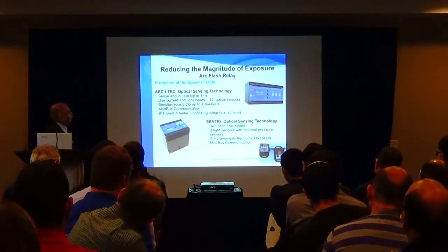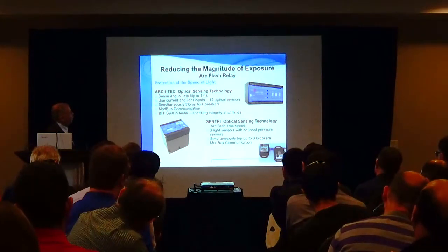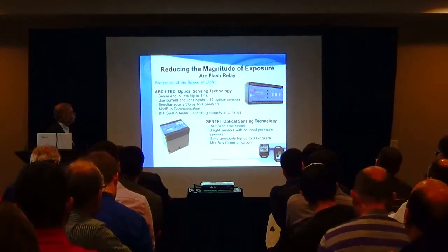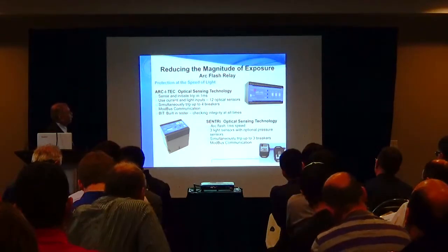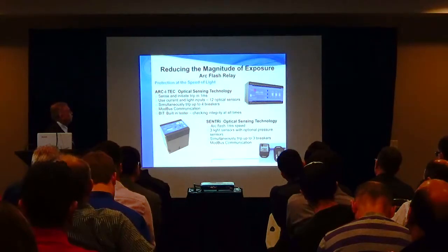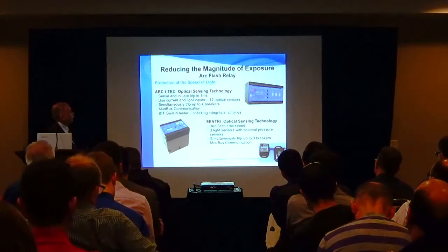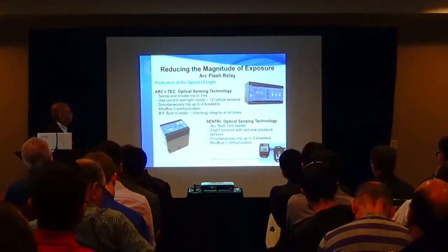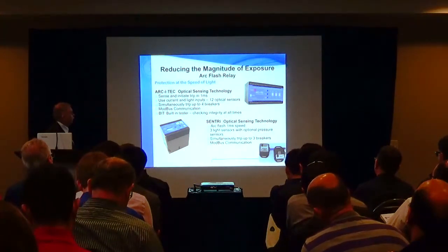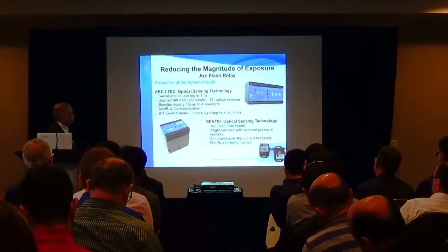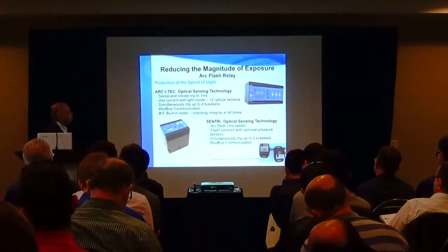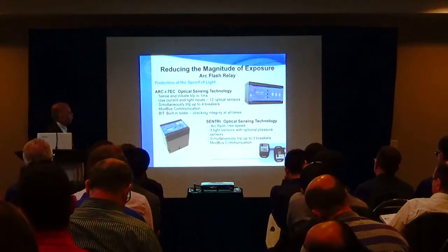We also make a dedicated arc flash relay with multi-circuits, 12 optical sensors in this relay. And this relay can use current and optical sensing as the AND function. It will provide a simultaneous trip output to up to 4 breakers, again with Modbus communication. The unit has a built-in test feature to check the integrity of the fiber at all times.